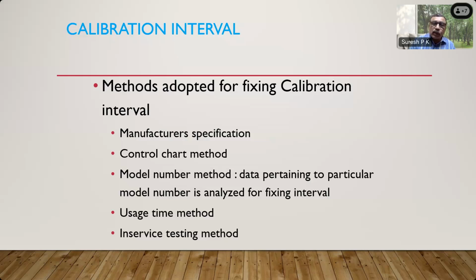Manufacturers specify so many things. Certain manufacturers say that it never has to be recalibrated, that the meter itself takes care of the calibration based on certain readings. I humbly disagree with that kind of specification, because you need calibration for the instrument. It's not because I used to work for FCRA and FCRA makes its income out of calibration. It is because the instrument can misbehave sometimes due to various reasons which are not defined or not known to us. Therefore, it has to be verified. There has to be some means to verify the flow meter once in a while. So at least once in a year.